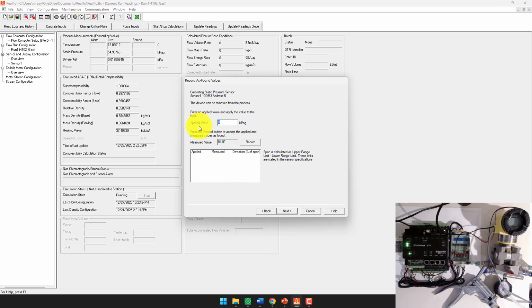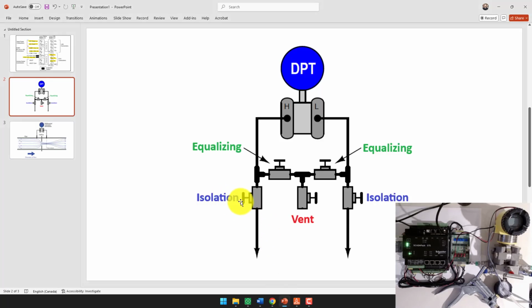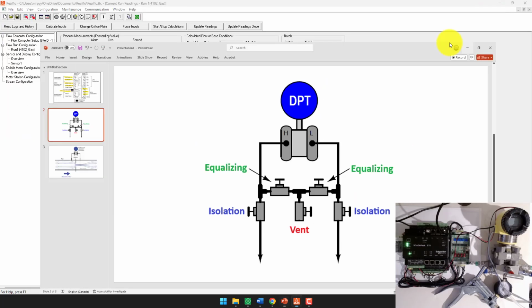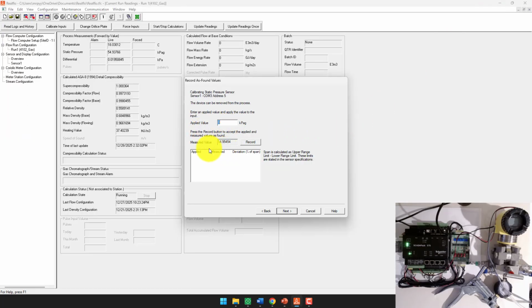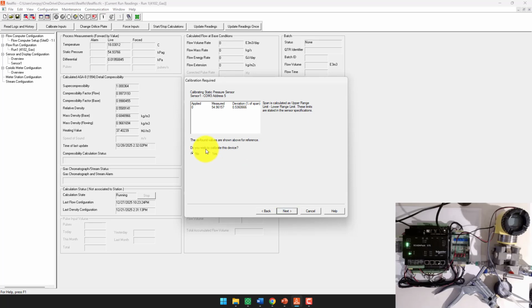So we're going to make the applied pressure zero, because right now we have the isolation valves open, the equalizing valves open, the vent open, and the pump that's connected to the vent depressurized here. We're reading a true zero, so what we're going to do is record that. So we'll go next. And it says, do you wish to calibrate the device? So we will go yes and go next.